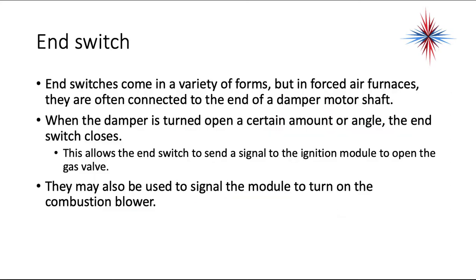The end switch comes in a variety of forms, but in forced air furnaces they're often connected to the end of a damper motor shaft. When the dampers open or turn to a certain angle, the end switch closes. This allows the end switch to send a signal to the ignition module to open the gas valve, and it may also be used to signal the module to turn on the combustion blower.